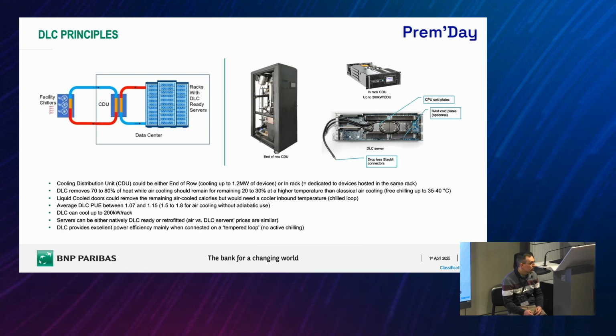The average DLC PUE is between 1.07 and 1.15. The 1.15 is what we have contractually with our suppliers, which means that they have much less in reality. They agreed to cap the PUE at 1.15, so it's not something that is not actually reachable. It's not a dream. We have this 1.15 in our contract, so you can aim at a maximum of 1.15. That's what we actually use in our business plans. As a comparison, we have 1.5 to 1.8 for our air cooling facilities, and we don't use adiabatic systems.